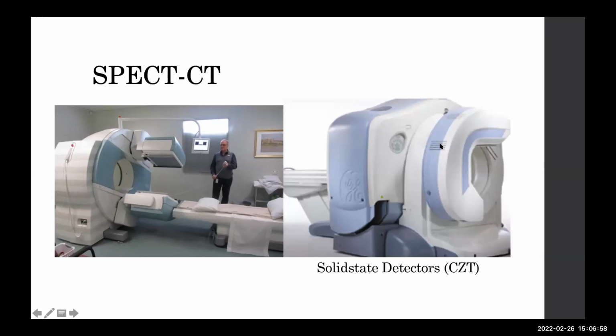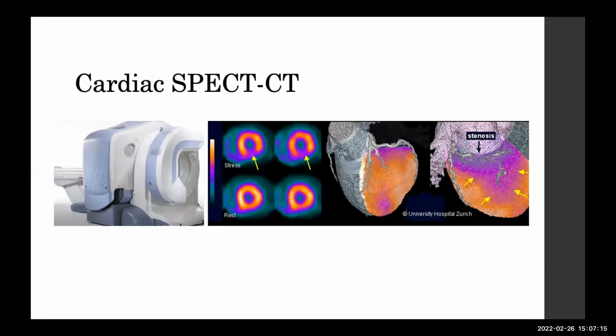This is the C-shaped detector placed here, and this is the diagnostic CT with solid state detectors. It gives you the advantages I have told before: faster acquisition, very good high resolution, high sensitivity images, along with very good CT images. Now this image was acquired on the SPECT-CT, the myocardial perfusion SPECT image. You can acquire the SPECT data as well as the CT coronary angio data in a single machine.